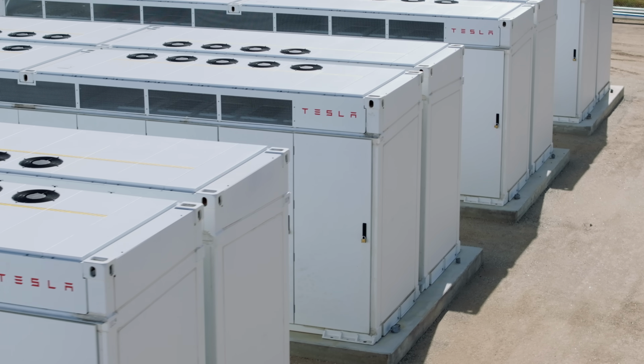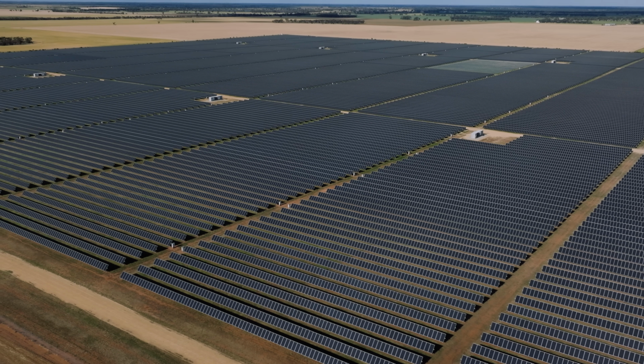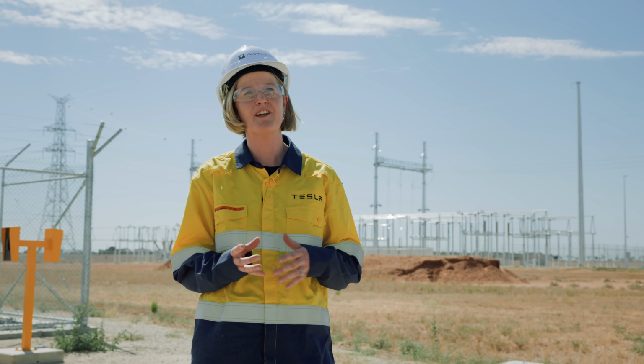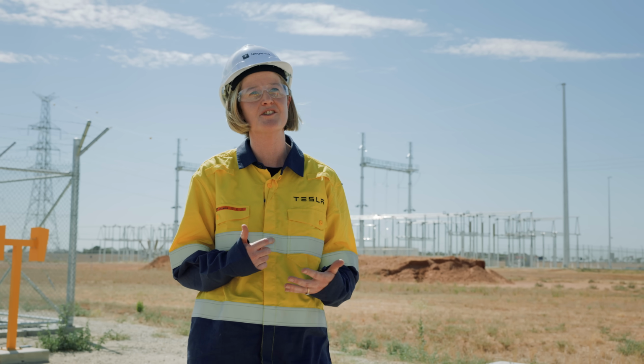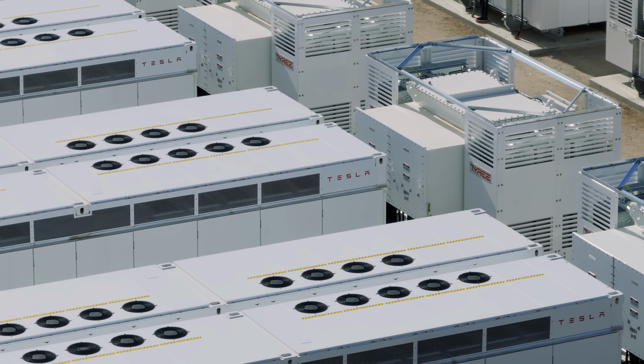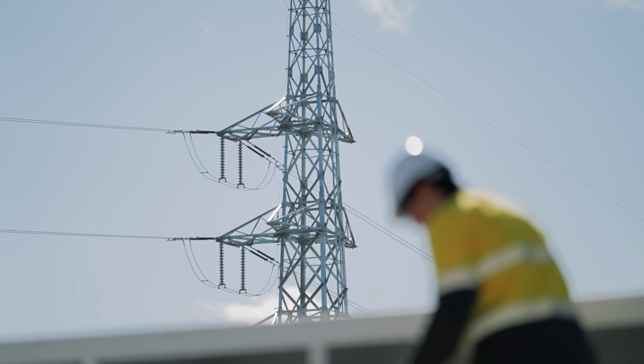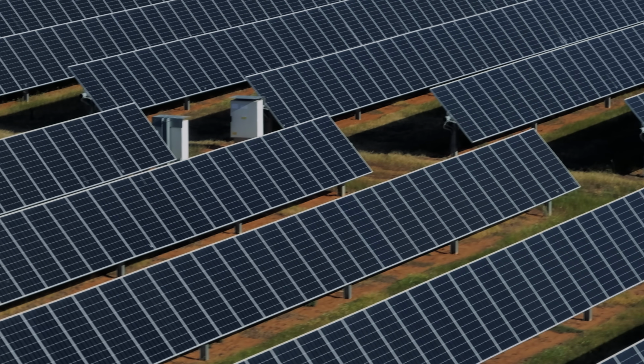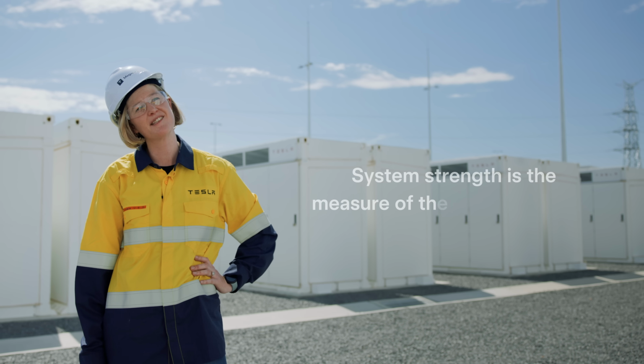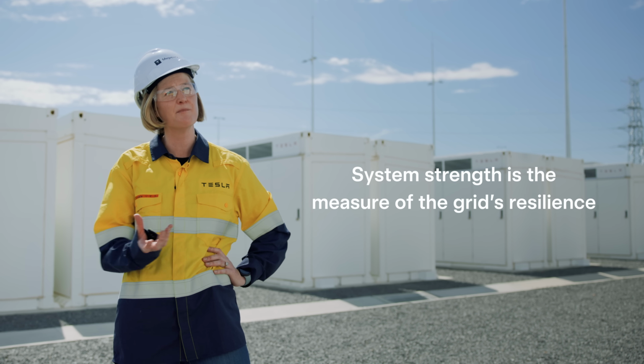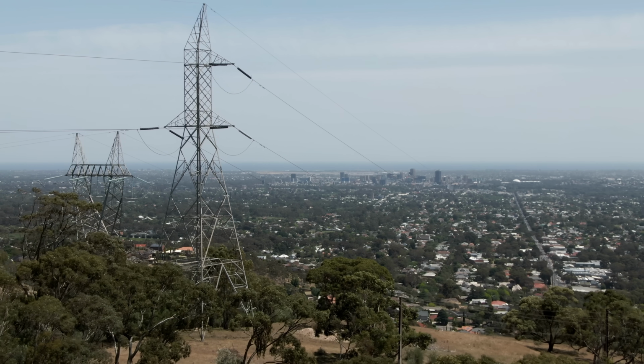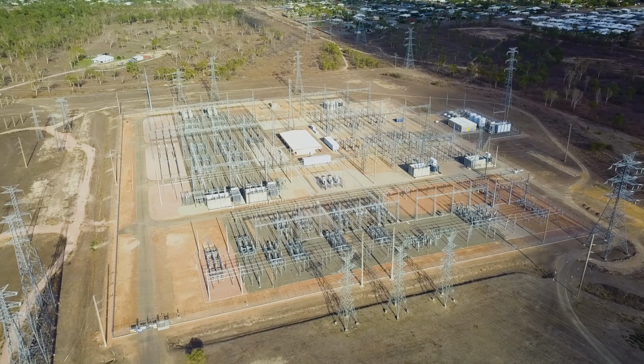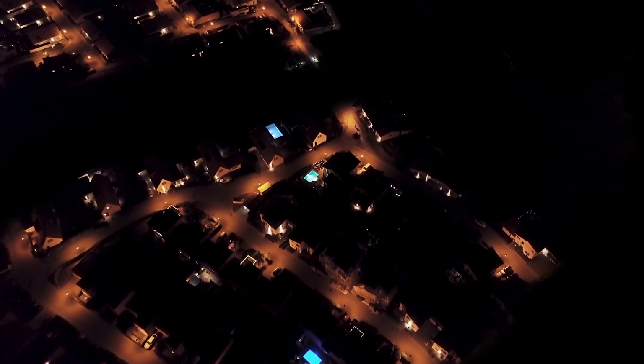There's an abundance of clean energy in the area, solar especially, but the transmission network faces operational challenges as a result of low system strength, which is limiting the amount of renewables that can connect to the existing infrastructure. System strength is the measure of the grid's resilience, its ability to resist changes to the network as a result of a disturbance, such as a fault or a sudden change of power on the network.